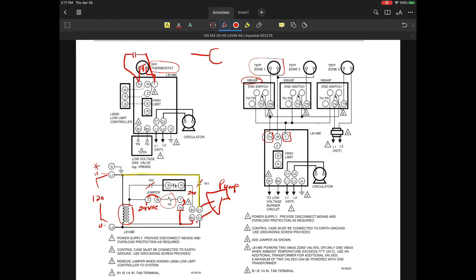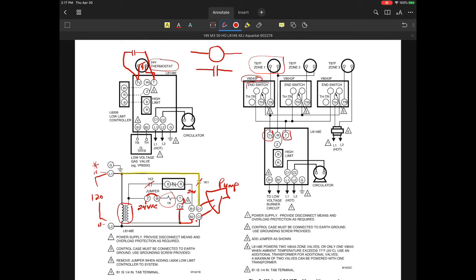And when the zone valve actuator gets powered up, it's going to power up a little motor inside those little zone valves. Now, in a zone valve, the way they work is you're going to have a little zone valve synchronous motor, and then typically we'll see a completely isolated set of contacts. So when they're talking about, in this device, this thing that's called an end switch, what they're getting at here is this little completely isolated set of contacts.